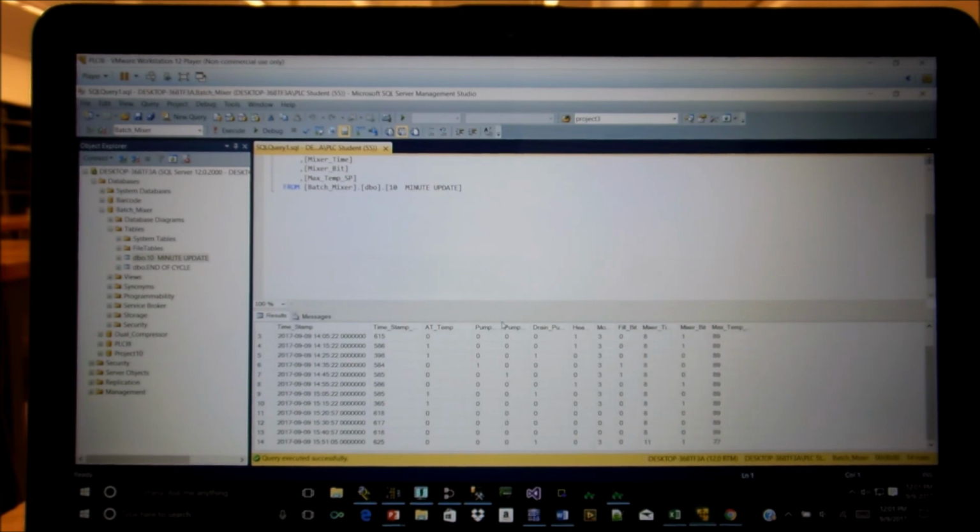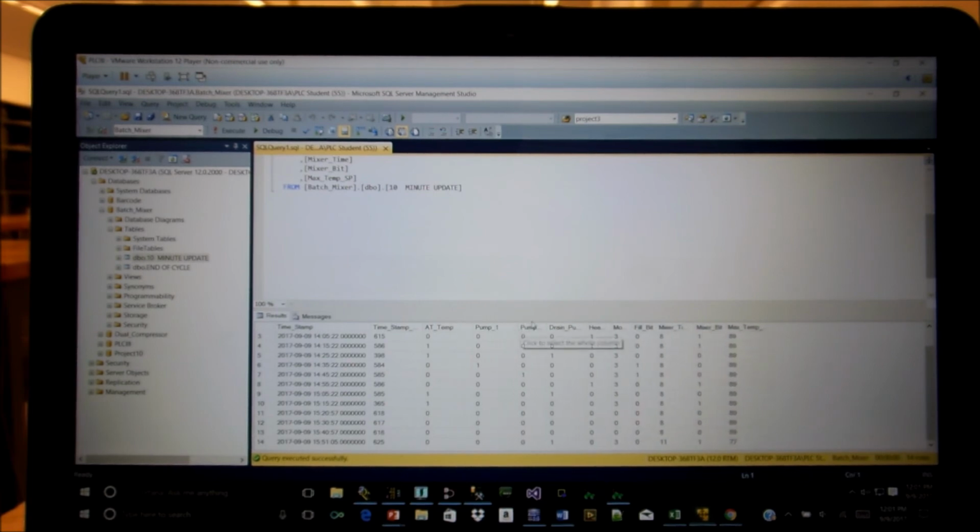And then some of these values are just telling if the pumps were on or off, and because it's just at 10-minute intervals, it's kind of random, and this tells us what the mode was in. Here, when it said 0, is where the system was actually in the off position.